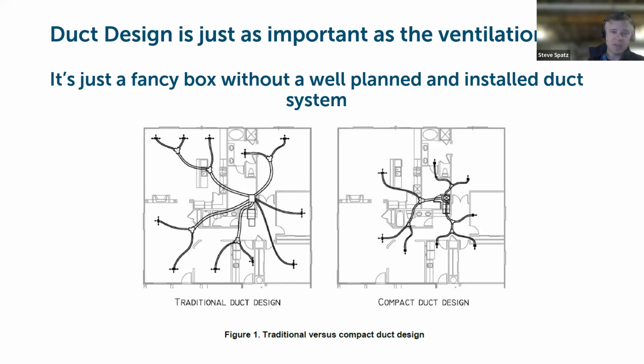And then you also have to have components in the duct design that will allow for adjusting those flows as you start to commission the system, because you don't want to have the intended 20 CFM being pulled from a bathroom and then realize that the way the system was installed is only allowing 4 or 5 CFM to be pulled from that bathroom. You want to make sure that you have the ability to adjust flows and you've got good duct design so you get the maximum potential out of the equipment once it's installed. So that's something to dig into a little bit more and consider for points.